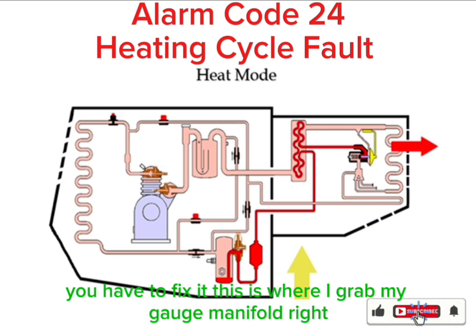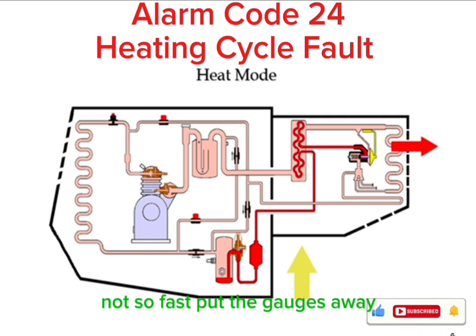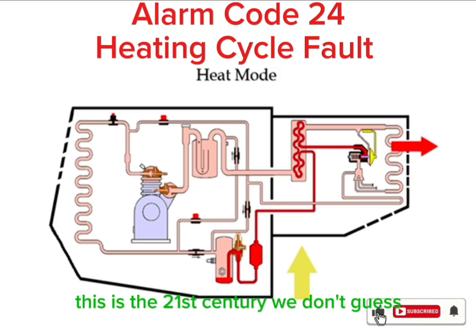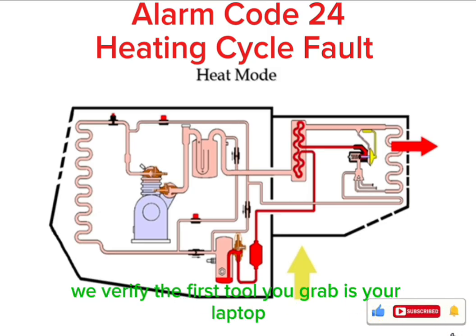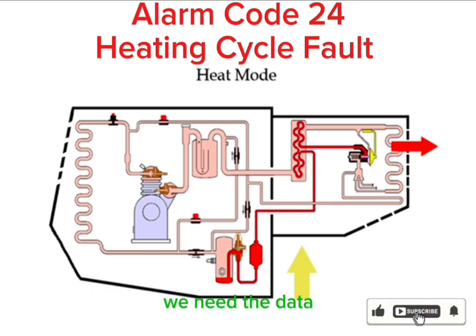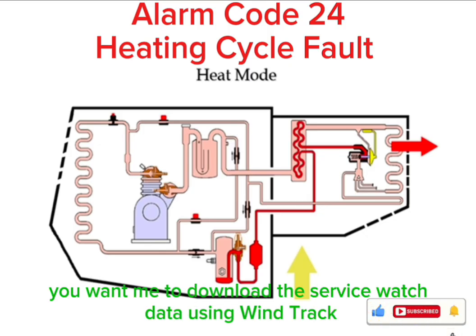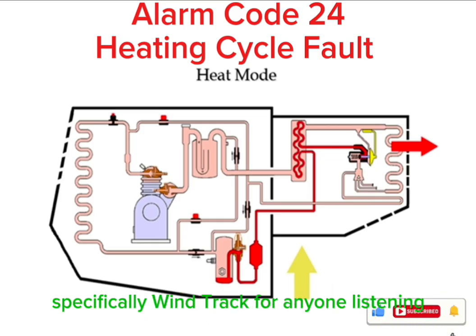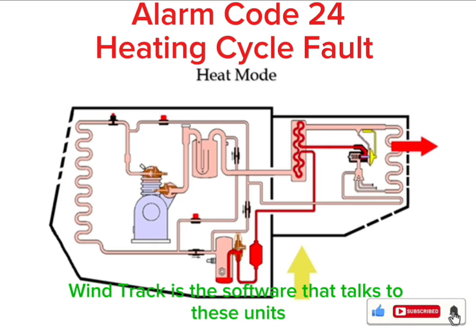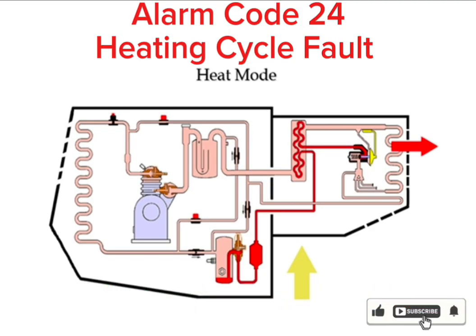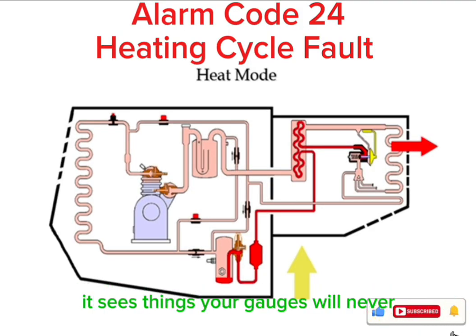This is where I grab my gauge manifold. Right? Not so fast. Put the gauges away. This is the 21st century. We don't guess, we verify. The first tool you grab is your laptop. We need the data. You want me to download the service watch data using WinTrack? Specifically WinTrack. For anyone listening, WinTrack is the software that talks to these units. It's the black box flight recorder. It sees things your gauges will never, ever see.